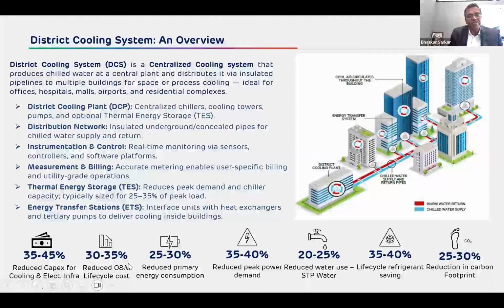The second is that these plants require very low maintenance. These are large plants which are almost maintenance free compared to the conventional VRF or the split AC or air chiller systems, which require a significant amount of maintenance cost throughout their life cycle. And also the life cycle period of those equipment is lesser. For split, maybe 8 to 10 years, for VRF similar, and for air-cooled chillers it may be 12 to 15 years, but in DCS the chillers last 25 years and plus. So there is an overall life cycle cost reduction by 30 to 35%.